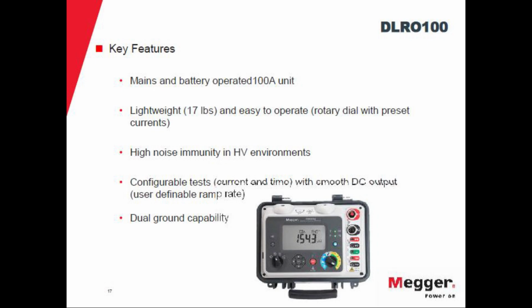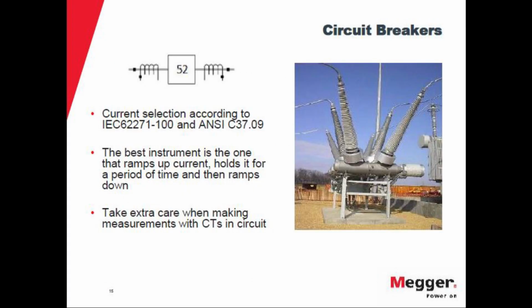And one other feature of this instrument is that you can have the sample that you are testing connected to ground on both sides. This is a very specific application for breakers. With this type of breakers, the safety procedures always ask you to ground both sides of the breaker, because there's going to be a lot of induction and noise in the substation, induced voltages. So both sides of the breaker should be grounded, and whenever you're running the test, you need to lift one of the grounds. That kind of defeats the safety purpose of those grounds. So with this instrument, you can still have the breaker grounded on both sides and run the test.